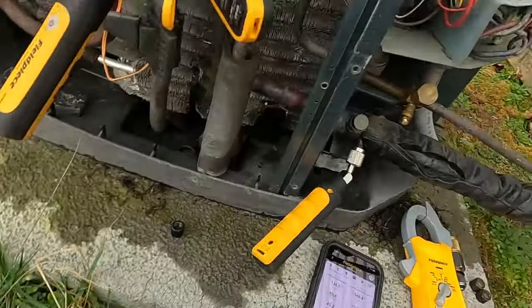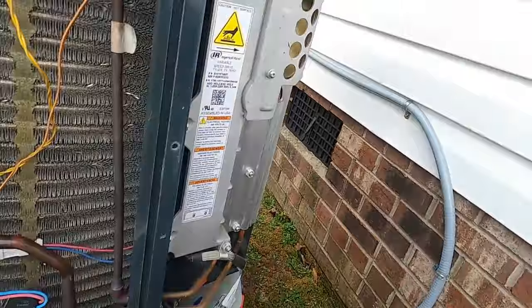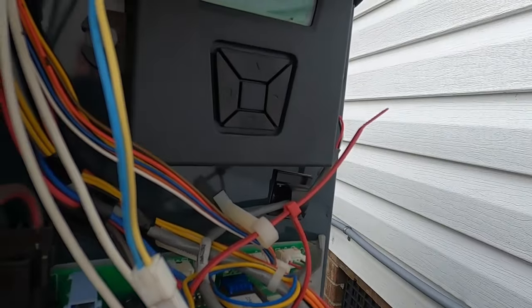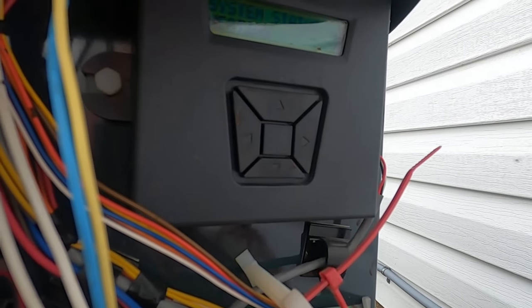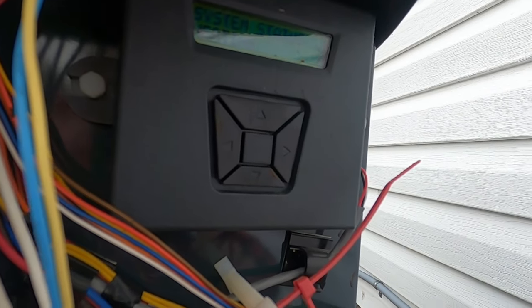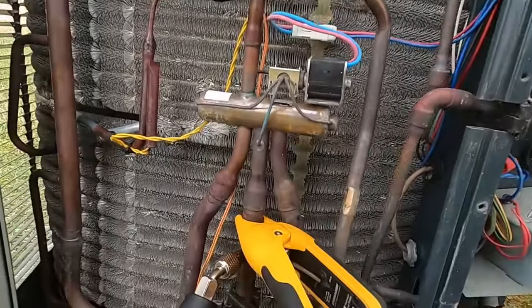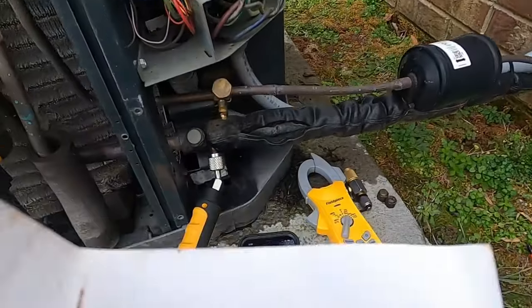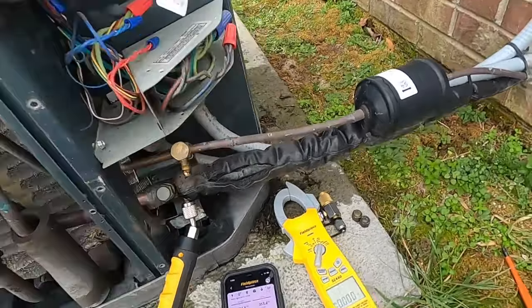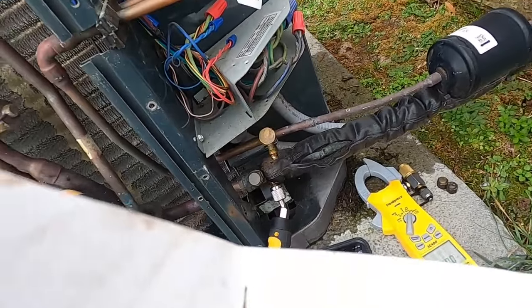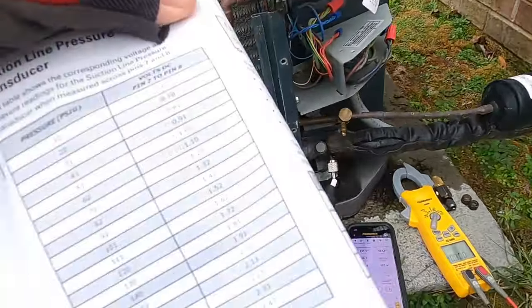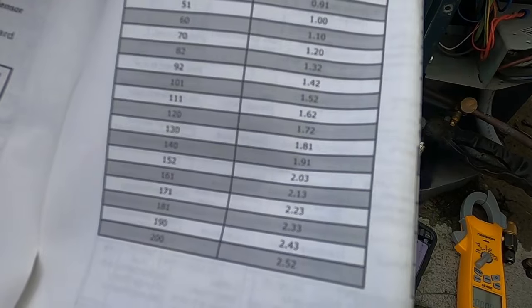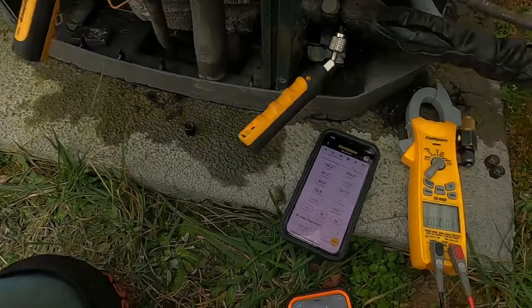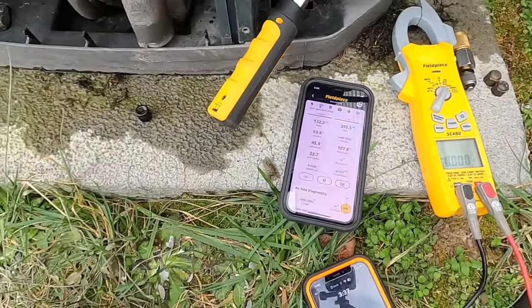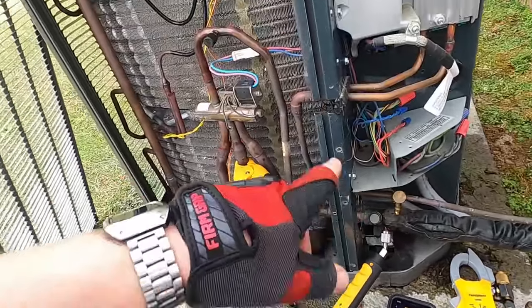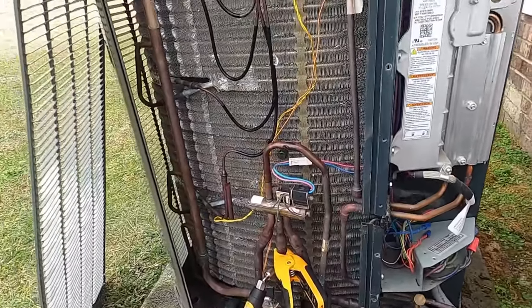So let's check it one more time. Maybe a little bit off. Now it's going up to 1.85. 1.85 is going to be up to 135, and we're up at 132. So the transducer is good. Make sure you're using the right chart when you're testing this stuff.